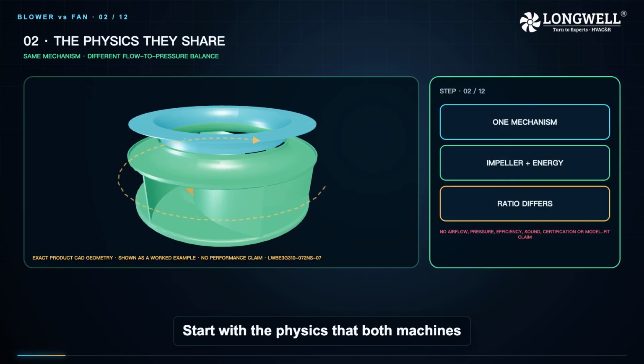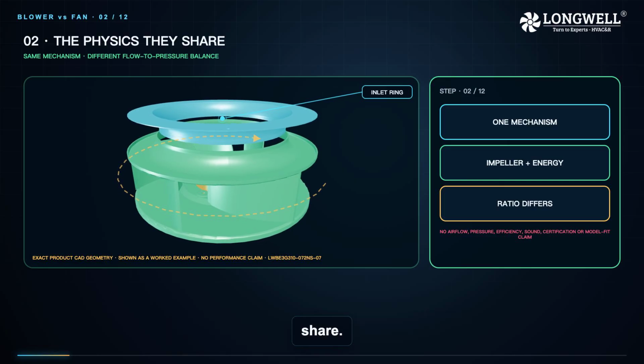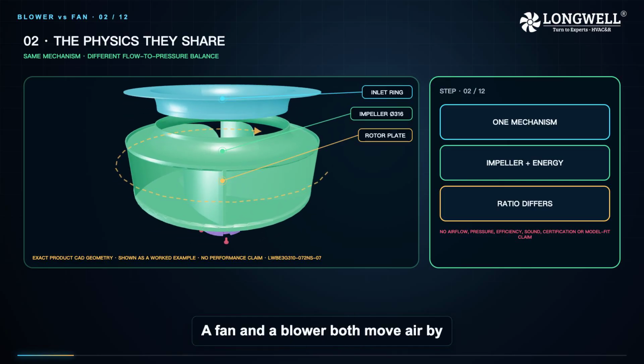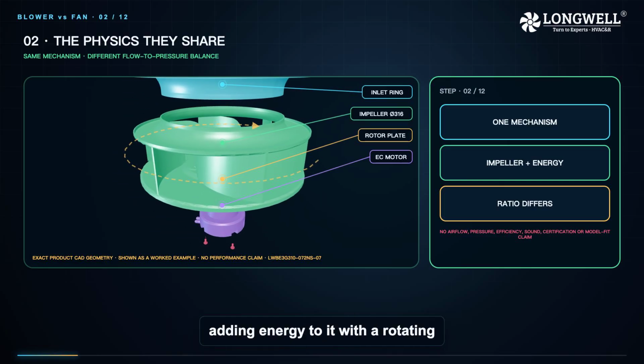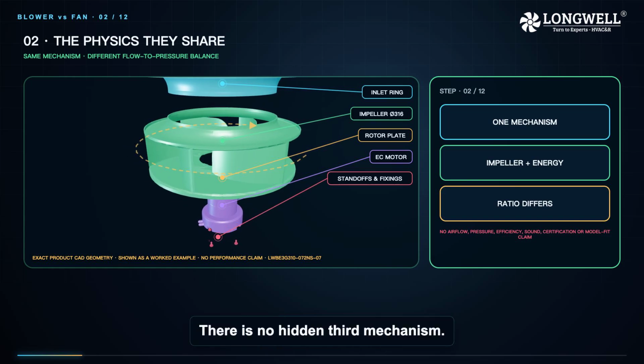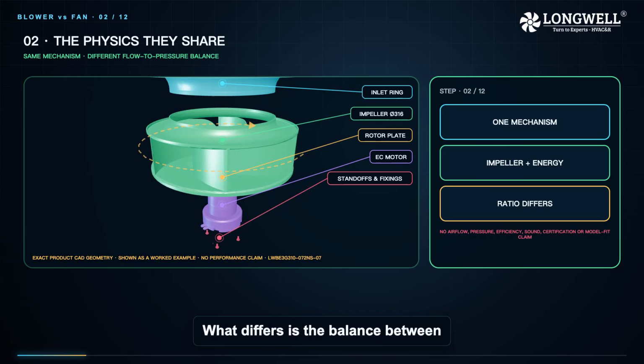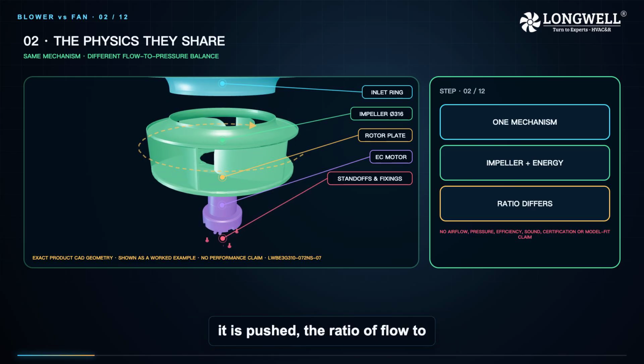Start with the physics that both machines share. A fan and a blower both move air by adding energy to it with a rotating impeller. There is no hidden third mechanism.